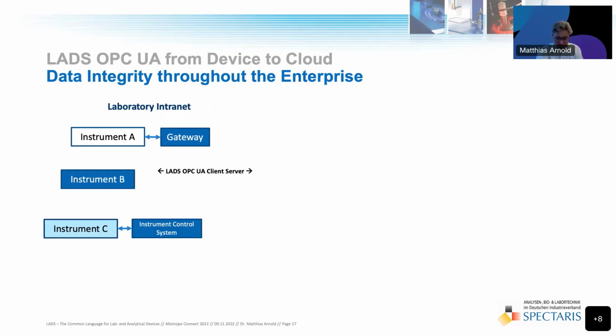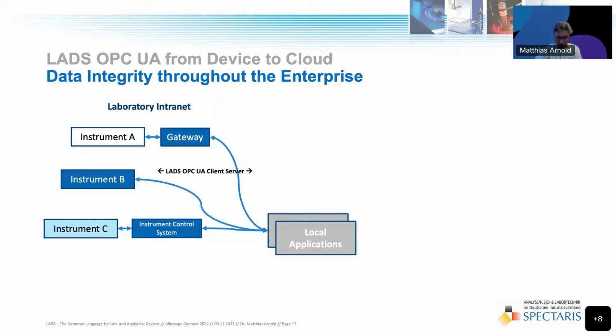Instrument C might be a modular analyzer, which is controlled by an instrument control system software running on a PC. This instrument control system provides LADS OPC UA as well. Local applications installed within the laboratory utilize LADS OPC UA client-server protocols to process the information provided by instruments A, B, and C.